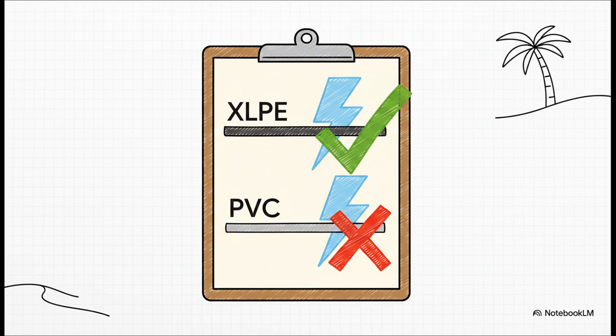While standard IEC 60502-1 covers both PVC and XLPE for those lower voltages, IEC 60502-2, which covers up to 30 kilovolts, focuses entirely on XLPE and EPR rubber. PVC is literally excluded from medium voltage applications by the standard. On top of that, regional utility providers like the Saudi Electricity Company, for example, enforce strict codes that mandate XLPE entirely for all underground utility routing.